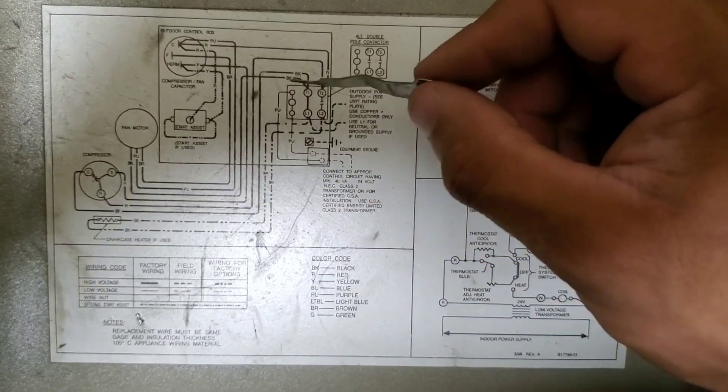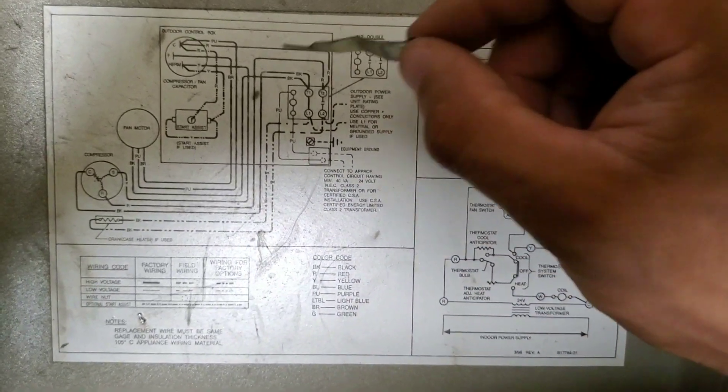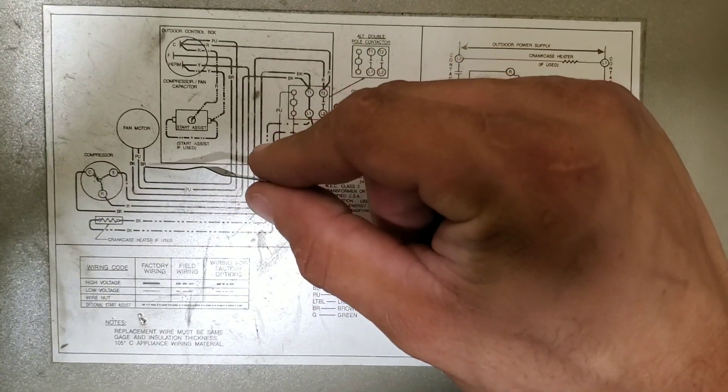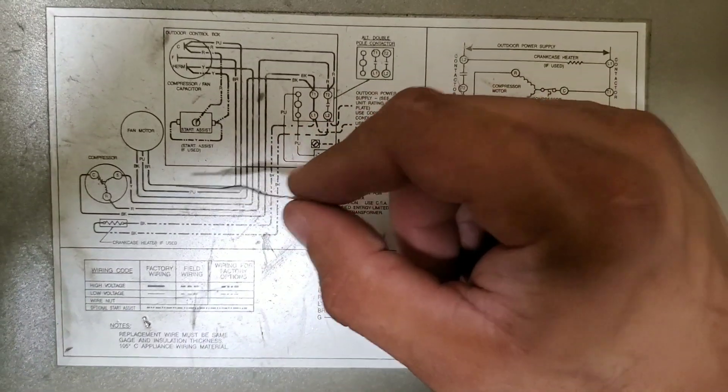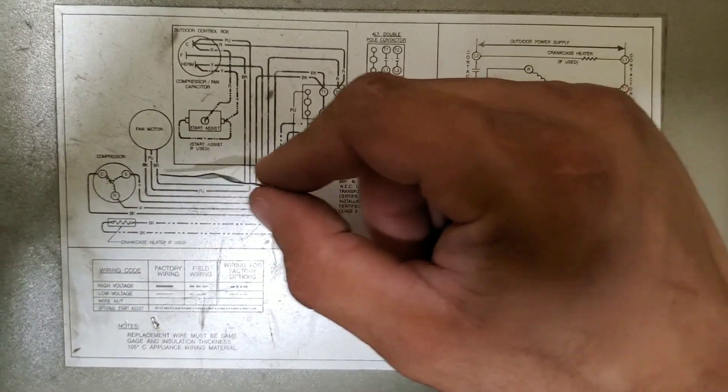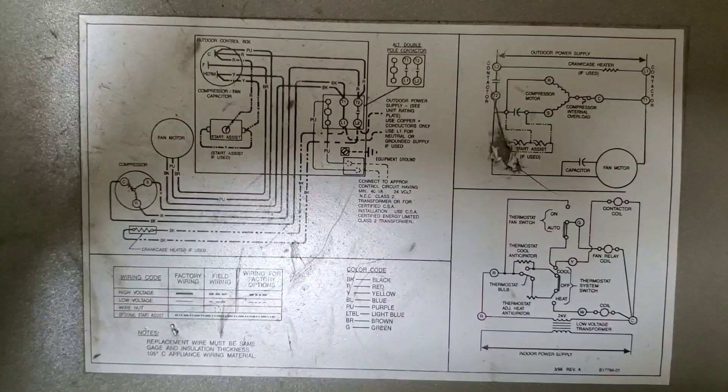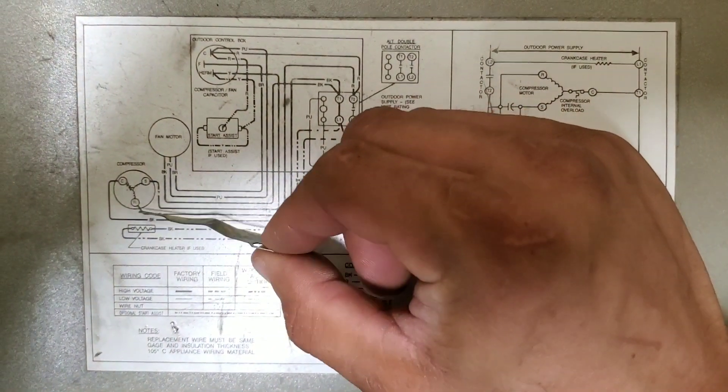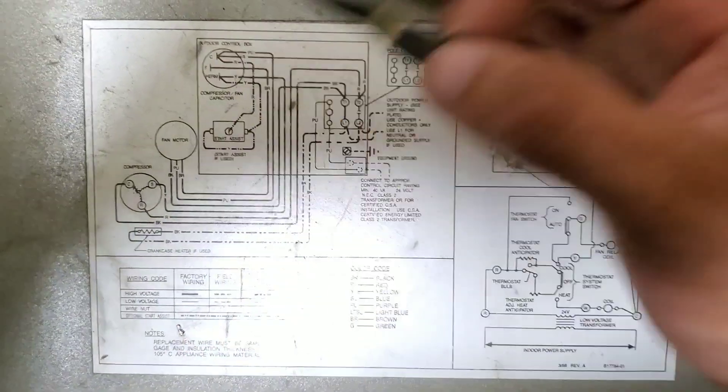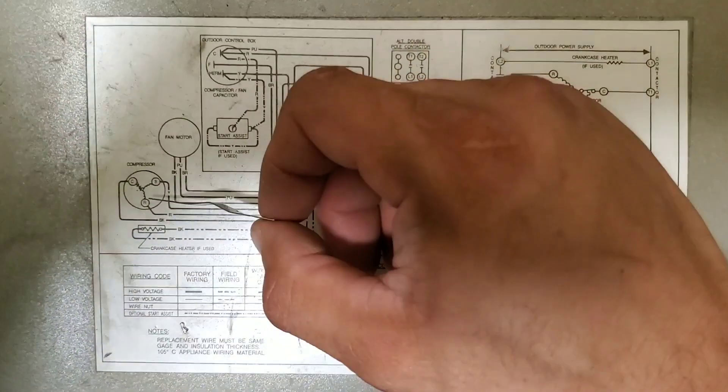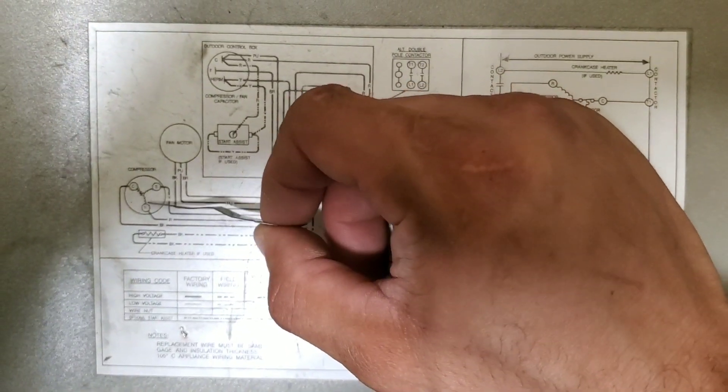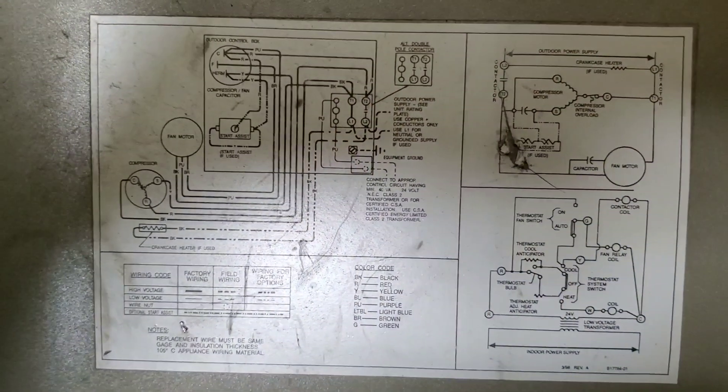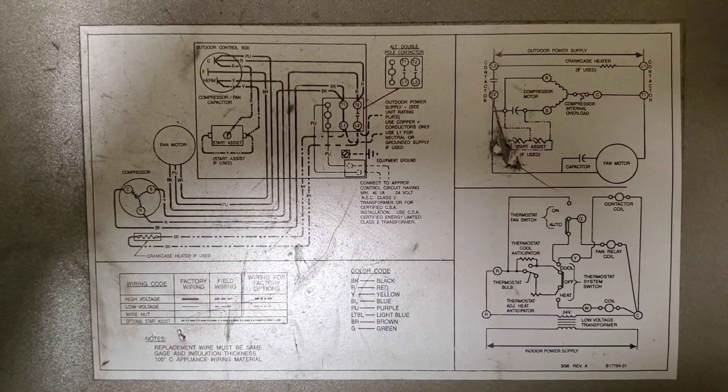This is why I try to discourage guys from learning or training to do it based off the coloring of the wires, because you don't know who did what before you got there. Your default for your mind and troubleshooting should always be to check the schematics. The schematics will tell you, it doesn't matter if you put one, two, or three compressors within 10, 15, 20 years - the schematics are always going to stay the same.